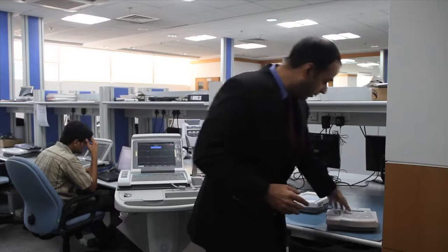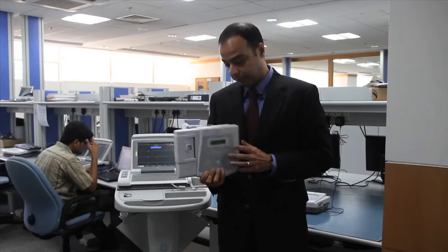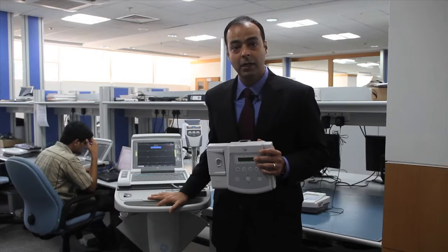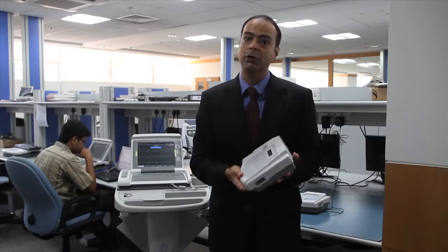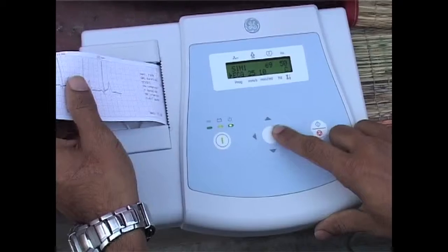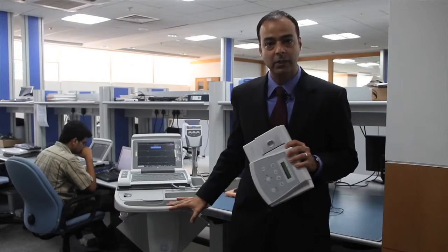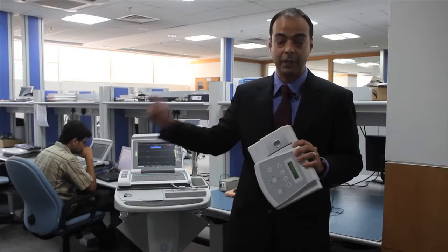The MAC 400 is what we came up with. This is an ECG machine, very much akin to the MAC 5500. It does a lot of what that does but also customizes in a way for the workflow we would encounter within a rural setting. Quality-wise, this does as good an ECG readout as that one. It may use fewer leads because we're using it more for screening rather than for diagnosis.